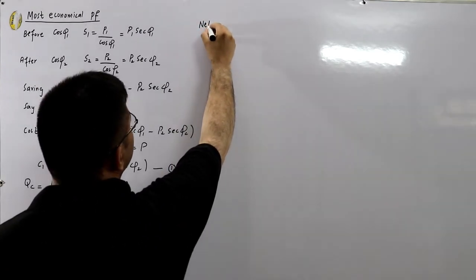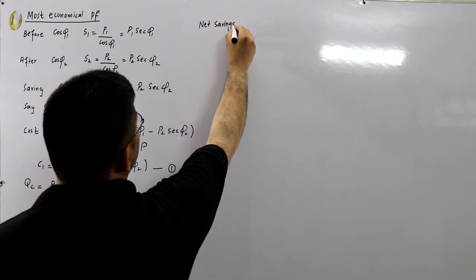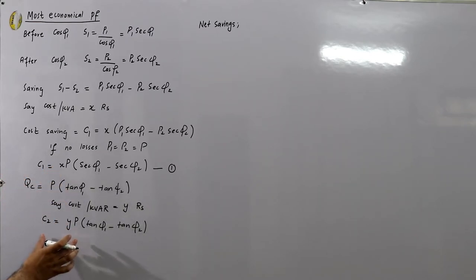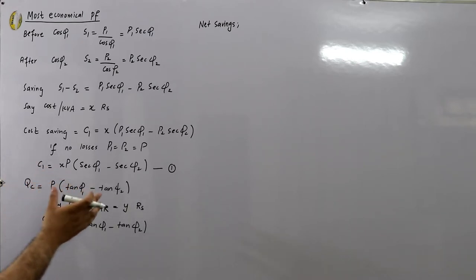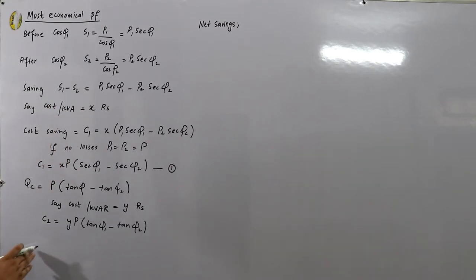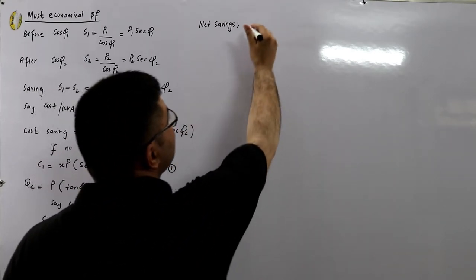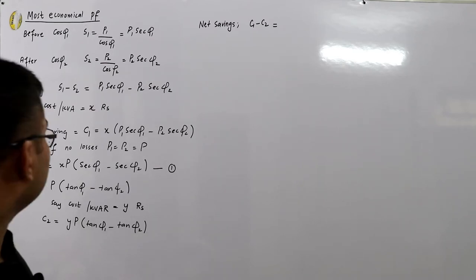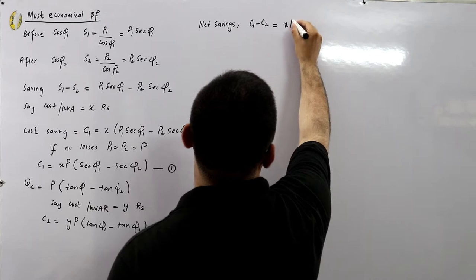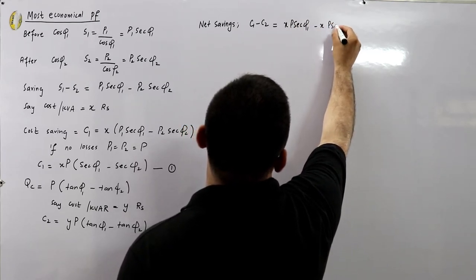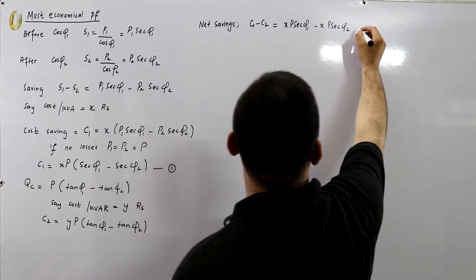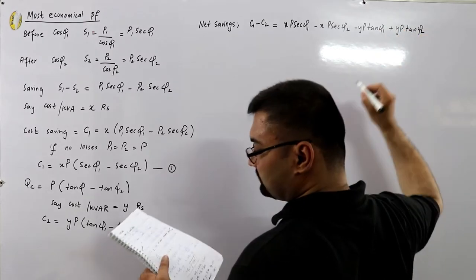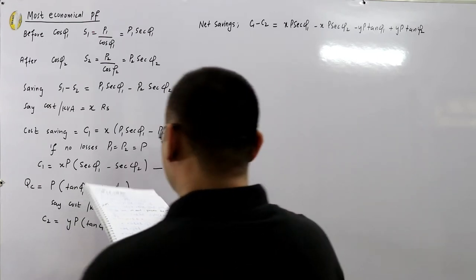The net savings equal C1 − C2. You have saved C1 by reducing kVA demand charges, and you are spending C2 on the power factor improvement devices. Expanding: Net savings = X×P×sec(φ1) − X×P×sec(φ2) − Y×P×tan(φ1) + Y×P×tan(φ2).